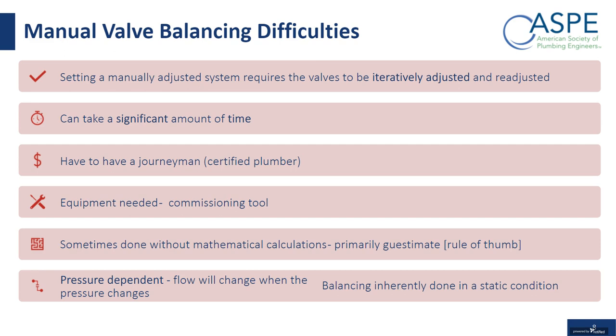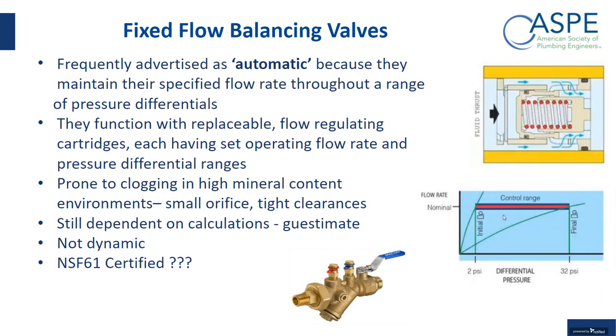And then they're pressure dependent, the whole system. So when you have manual balancing valves, if for some reason the pressure in the system changes, all the flow rates change, which could impact the balancing. So the next type of valve, what I call fixed flow or automatic or pressure independent, where you put a cartridge in there for a certain flow rate, they are used to maintain, again, a certain flow rate throughout the given branch or riser.